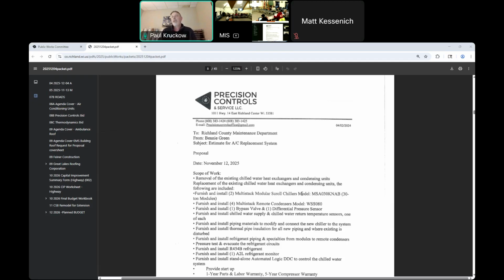consumption. So we're not just turning these chillers on and they're just running wide open and maintaining a set point. We'll be maintaining a chill water set point, but we'll also be looking at demand on the system so that if we don't have a heavy load in the building or a lot of call for chill water, we can scale things back and cut down the amount of energy being used. So that's all part of what's proposed in here. And that's at the bottom, the bulleted standalone Automated Logic DDC. That's what that portion will assist with.